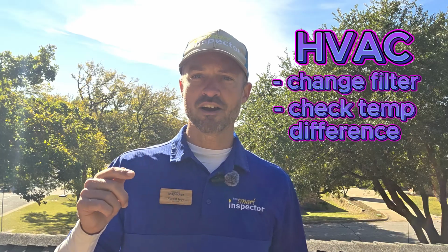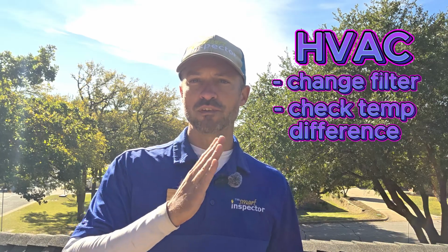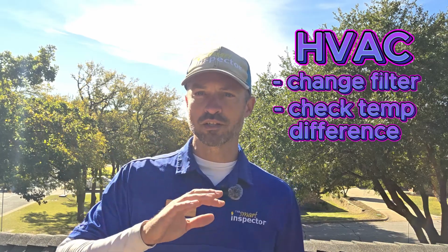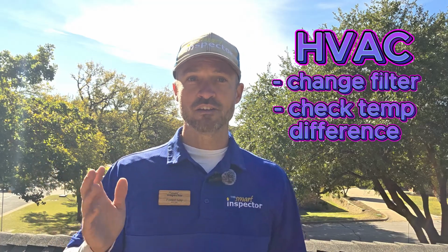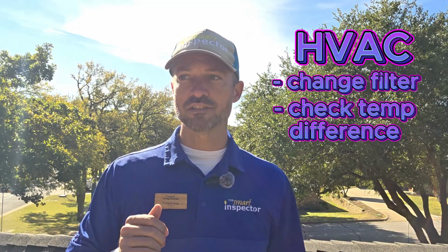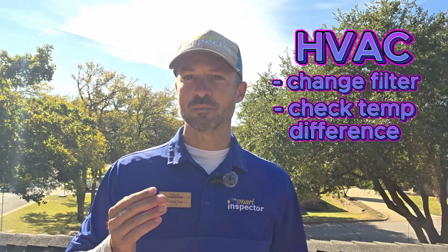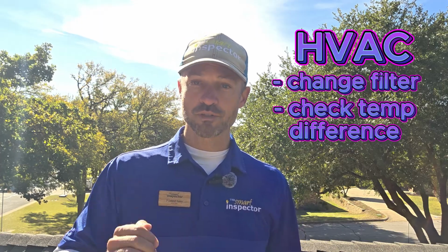That's the minimum we're looking for. And if you have your AC on, we're looking for anywhere from 15 to 22 degrees of cooling. We want it to cool off the air that much. If it doesn't do that, we write that up as a deficiency. You'll probably have to have somebody come do a tune-up on your system before your inspection.